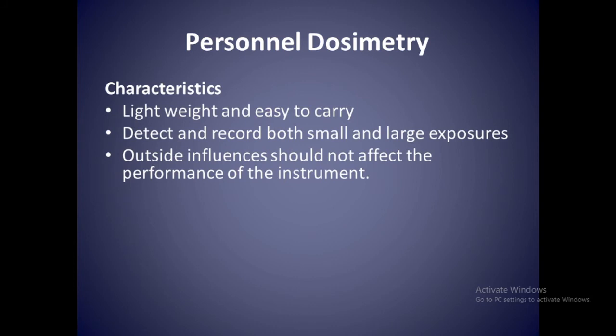A personal dosimeter should be lightweight and easy to carry, and be made of materials durable enough to tolerate normal daily use. The dosimeter must be able to detect and record both small and large exposures in a consistent and reliable manner. Outside influences such as very warm weather, humidity, and ordinary mechanical shock should not affect the performance of the instrument.